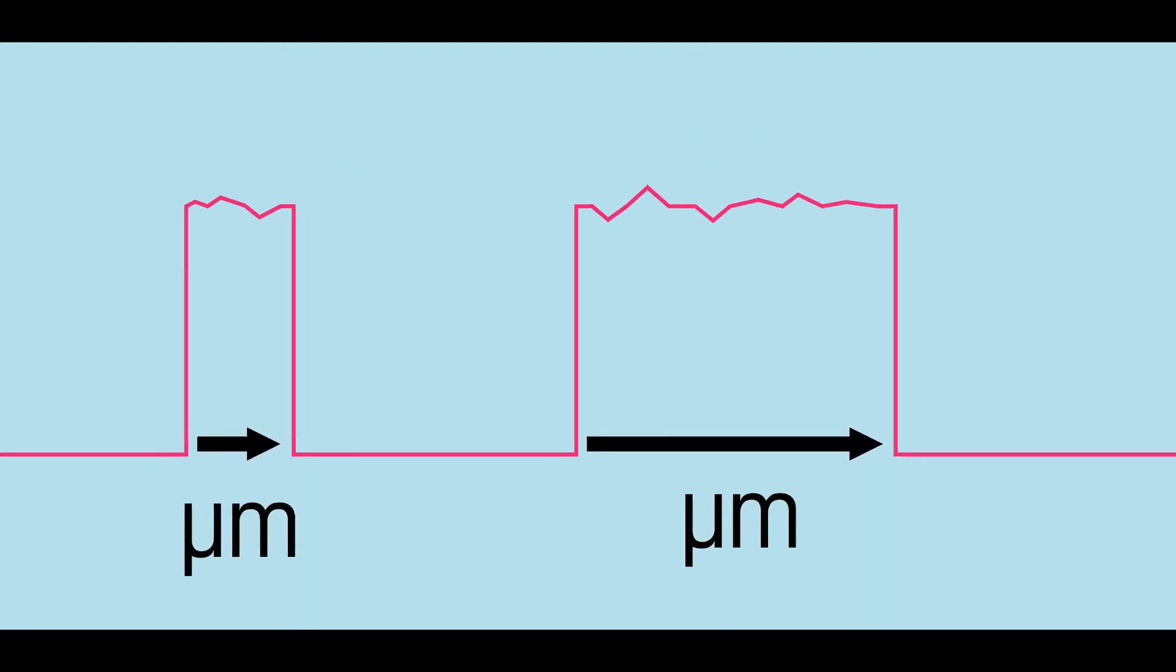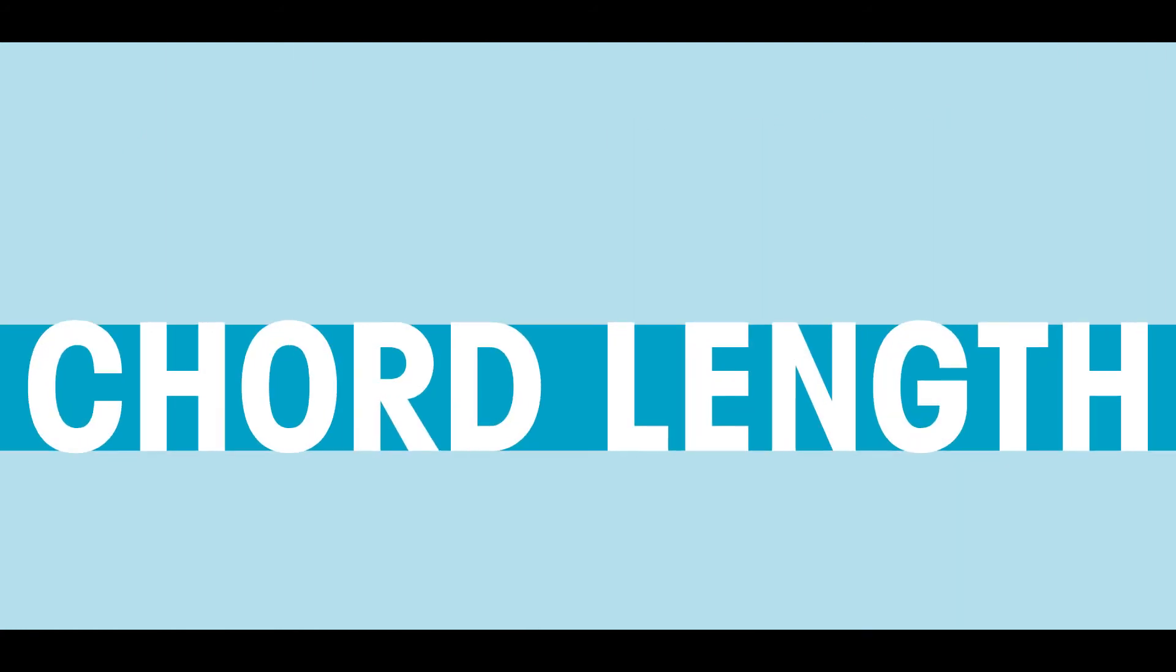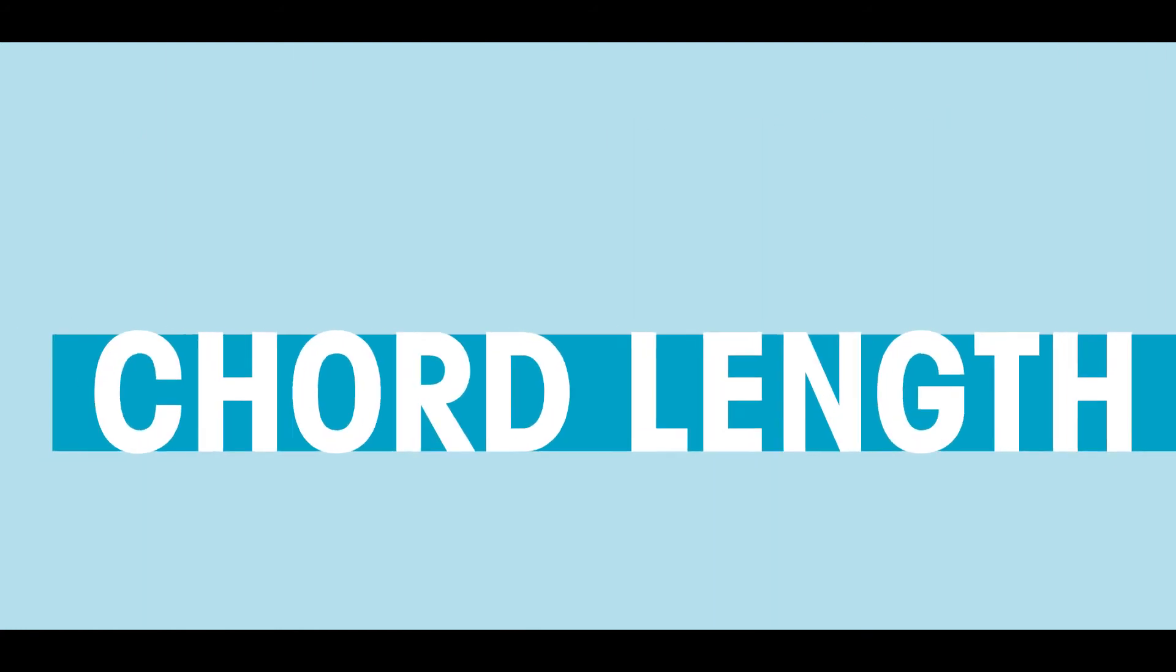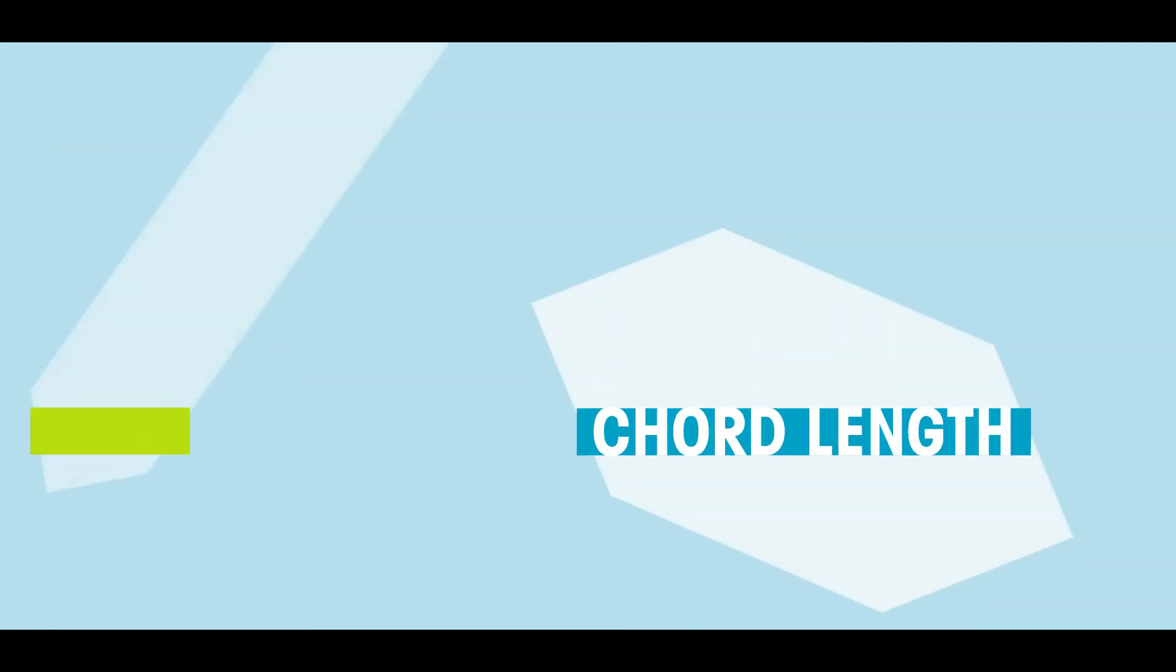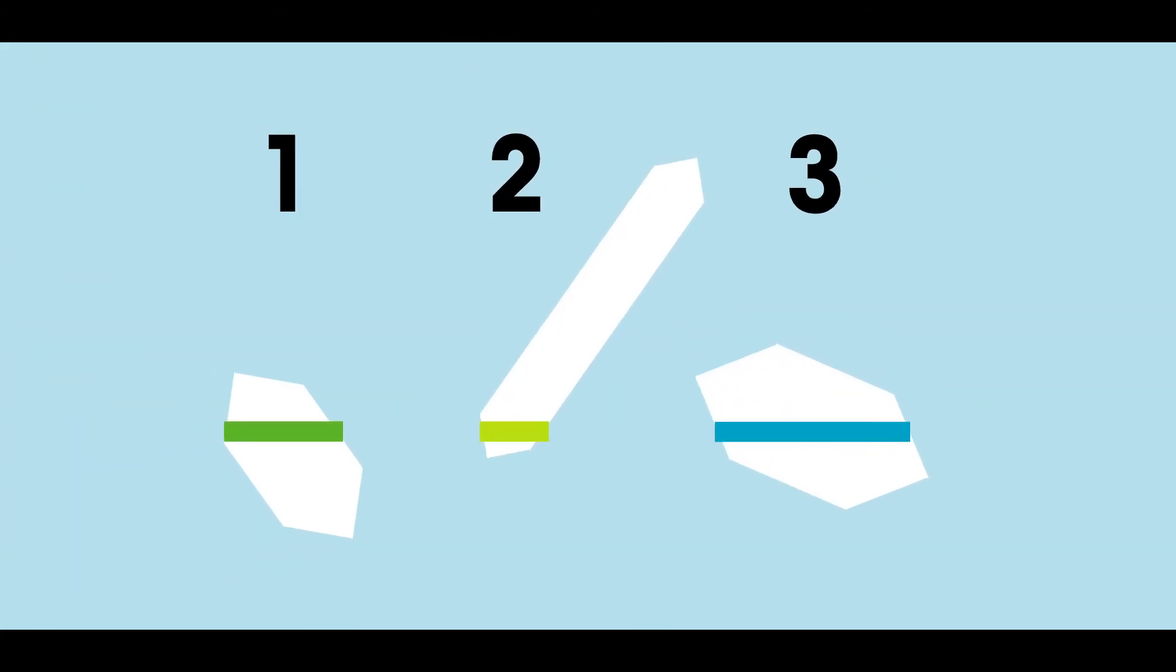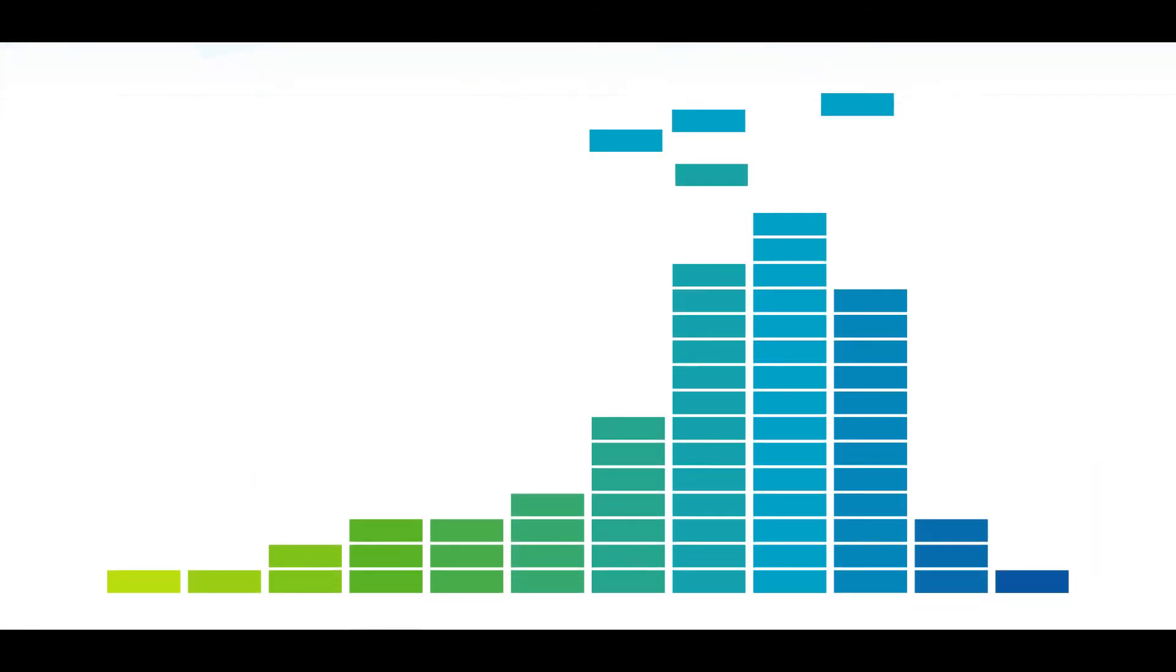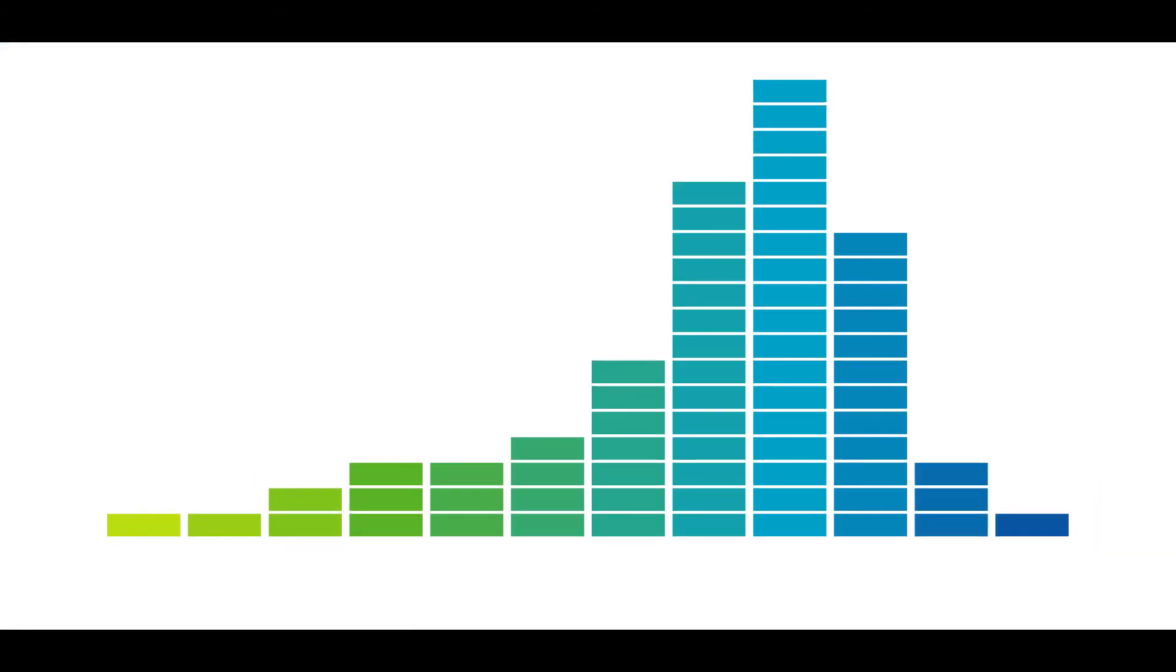This distance is defined as the chord length, a fundamental measurement of the particle related to particle size. Typically, thousands of particles are counted and measured per second, allowing a precise and highly sensitive chord length distribution to be reported in real time.